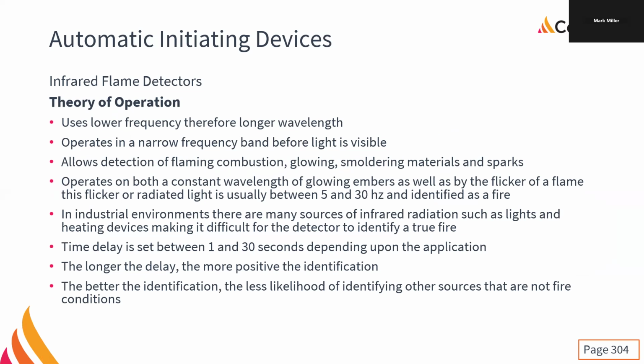Of course, infrared flame detectors, when we were testing them, we had to use a different ray gun, because that's shot in the infrared spectrum, not in the ultraviolet spectrum. It's a lower frequency, so it's a longer wavelength. It's going to pick up flaming combustion, glowing, smoldering materials, and sparks, right? Because it's a lower frequency, it's actually less heat, less intense. It picks up the constant wavelength of the glowing embers, but it also picks up the flicker of flame. It's really good at that.